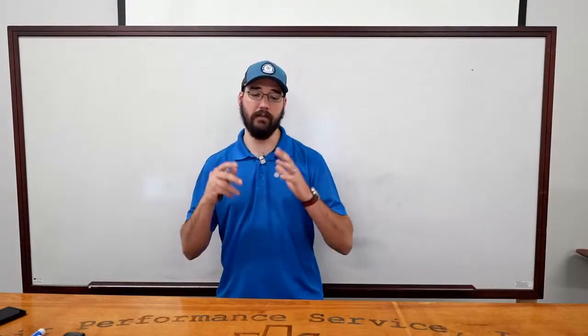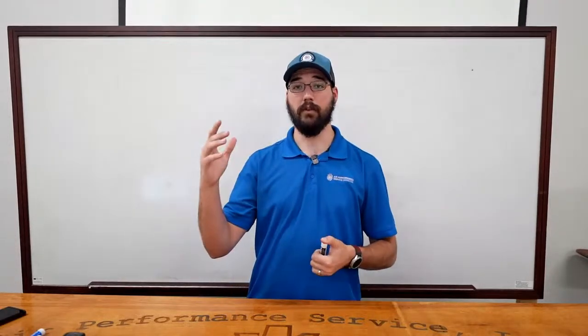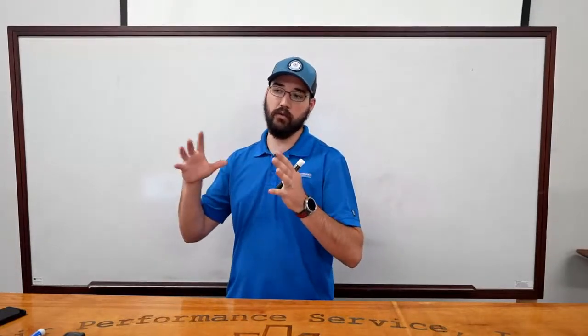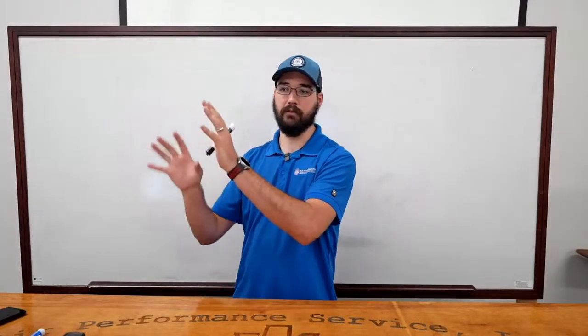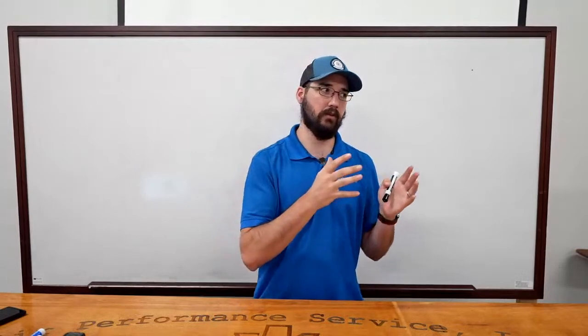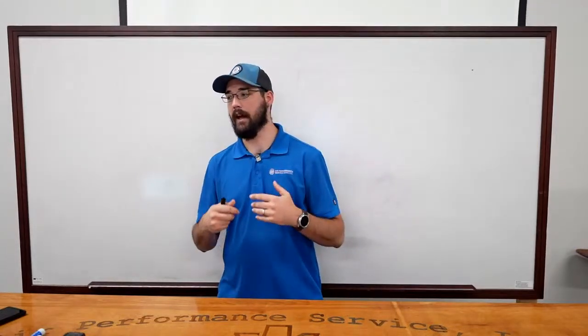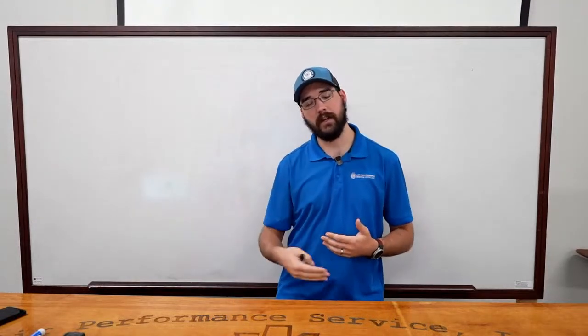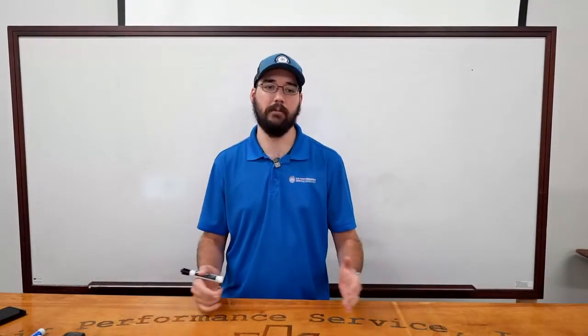And even myself, I have a slightly different mentality when I'm walking up to that versus whether it be an RTU, a split system, or a chiller. Most of those others, I can use a lot of the same basic fundamentals and get a lot further and not have to really rework my mindset. But when I start walking up to a VRV machine, I know that I'm going to have to take a little bit of a different approach. It's because of the fundamental design of what we're dealing with. It's using all the same science at the end of the day, but it's doing it in a different way.